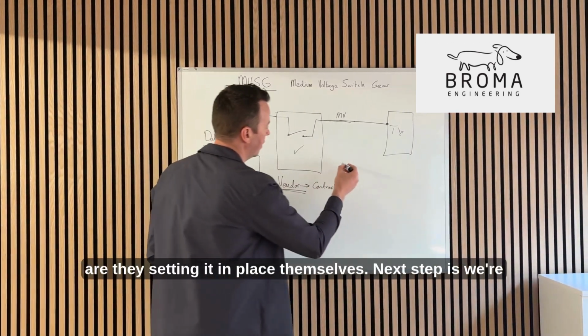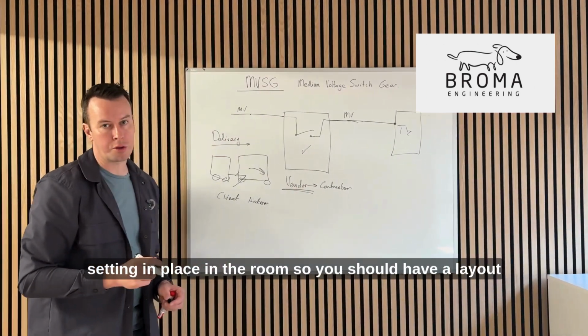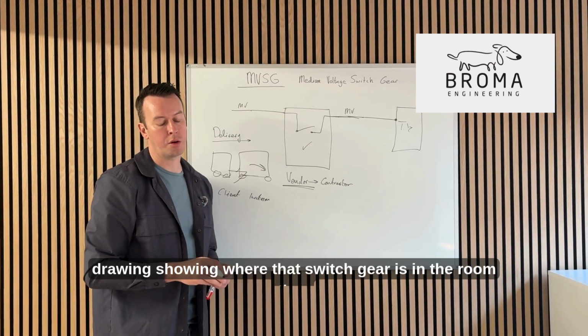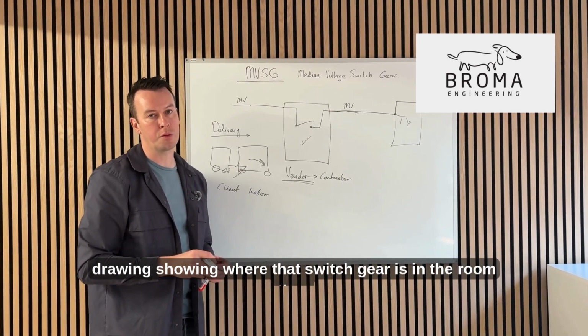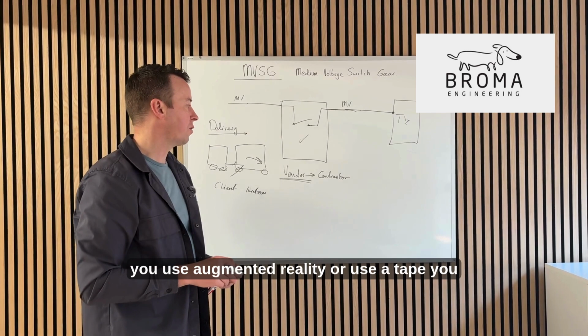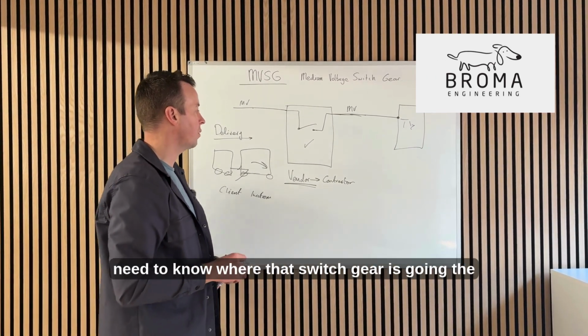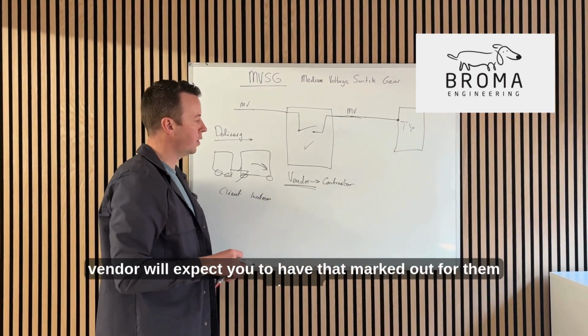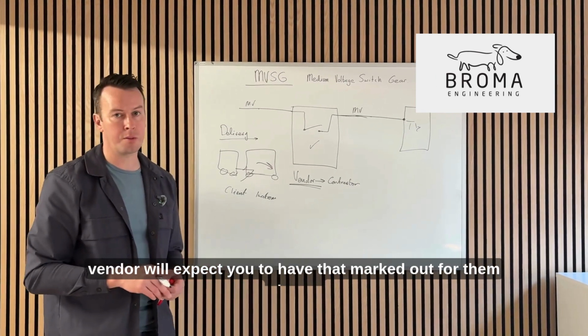Next step is we're setting it in place in the room, so you should have a layout drawing showing where that switchgear is in the room. Then a set out engineer, or you use augmented reality, or use a tape. You need to know where that switchgear is going.